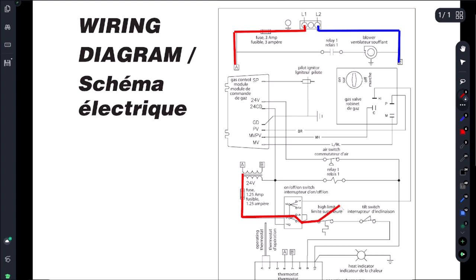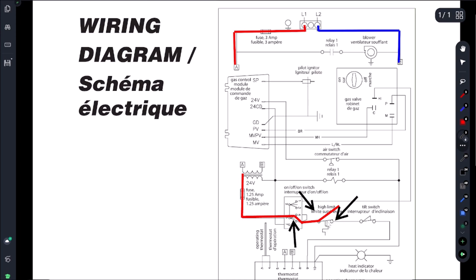I'm testing potential difference, so I'm testing from this point to this point. If we had zero volts it tells me the switch is closed or we don't have power coming through - that means we would have lost power somewhere on this switch. But the fact that I'm getting 28 volts potential difference is telling me the high limit is open. We're only at 200 degrees - the high limit should not be open. So that means the high limit is faulty.